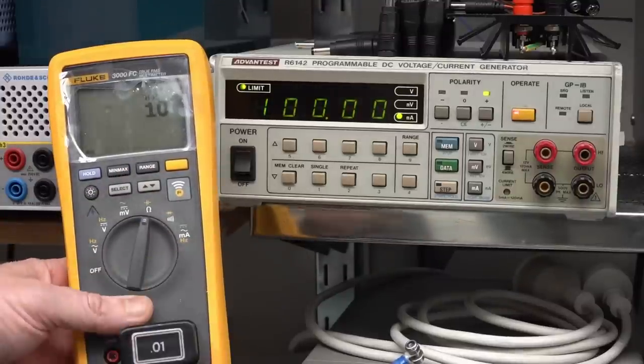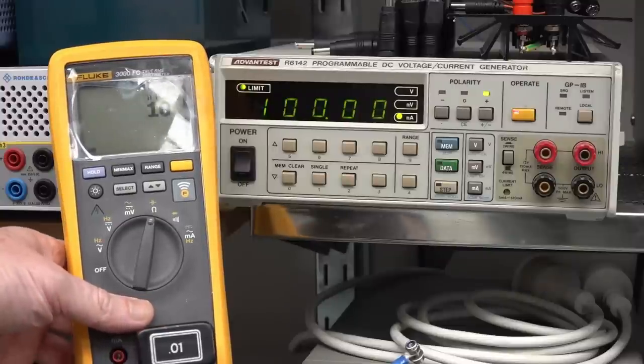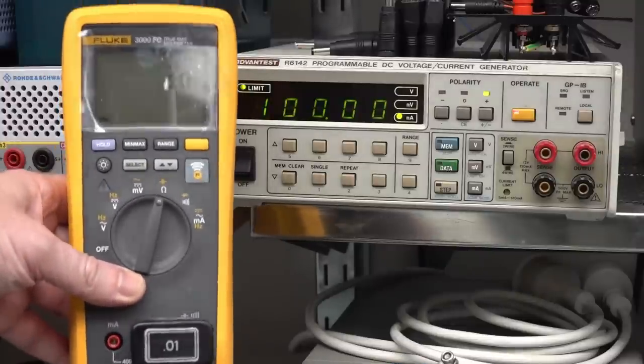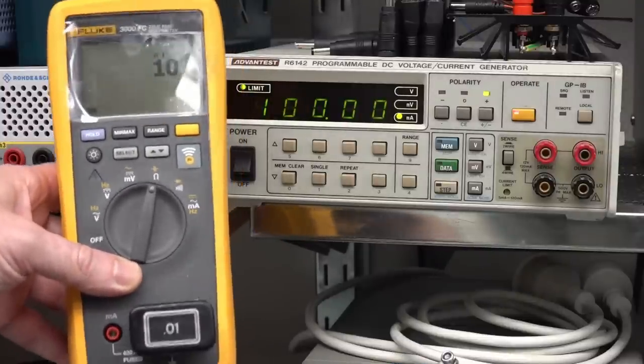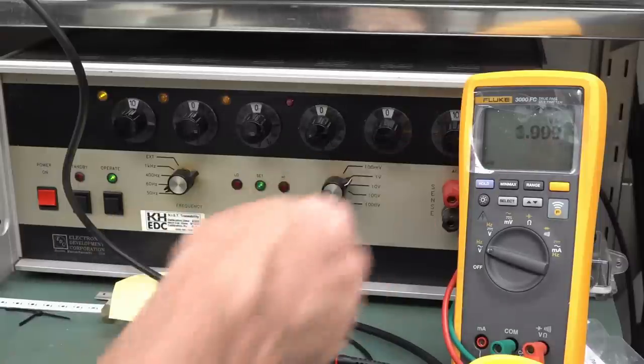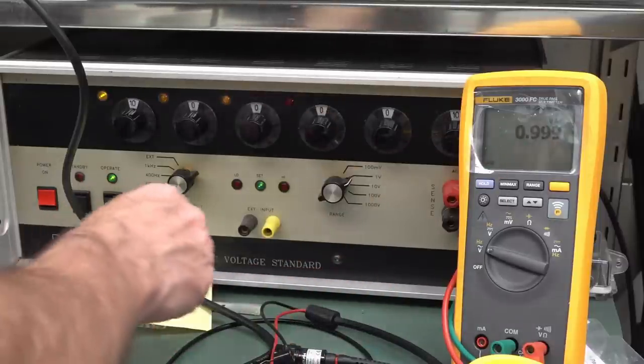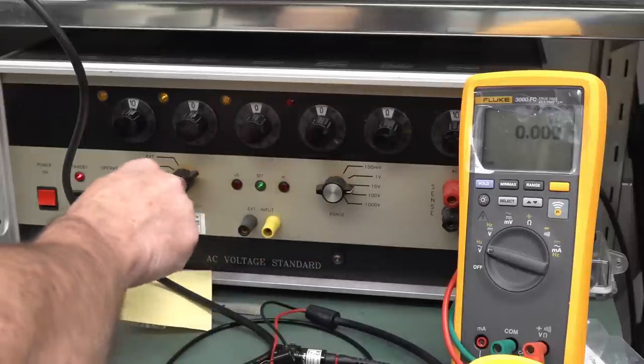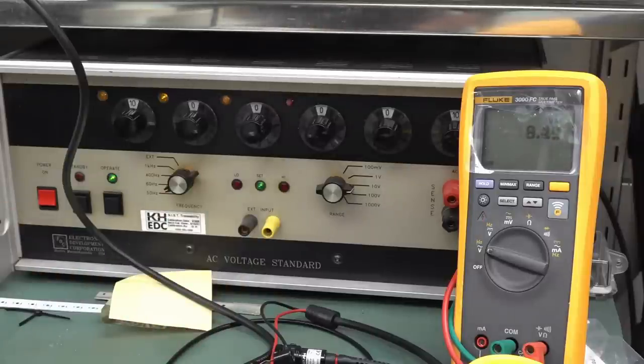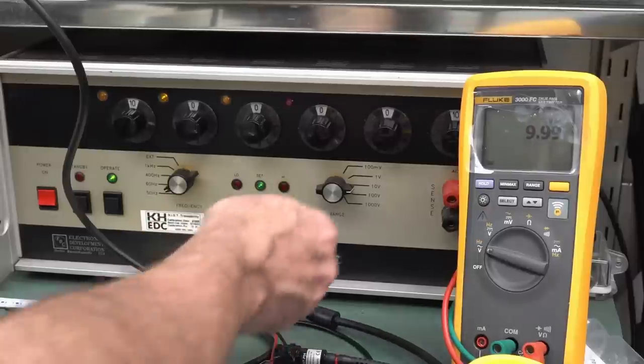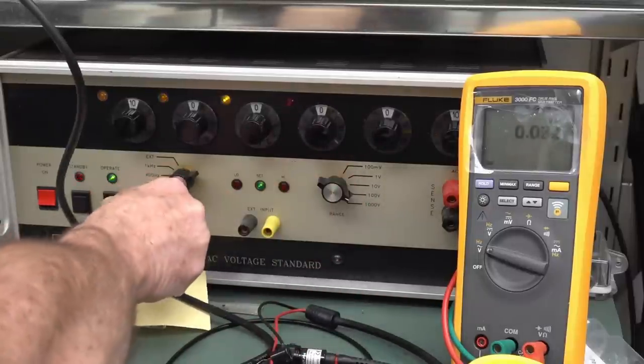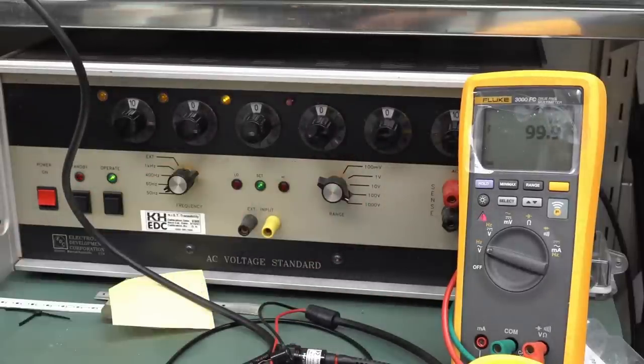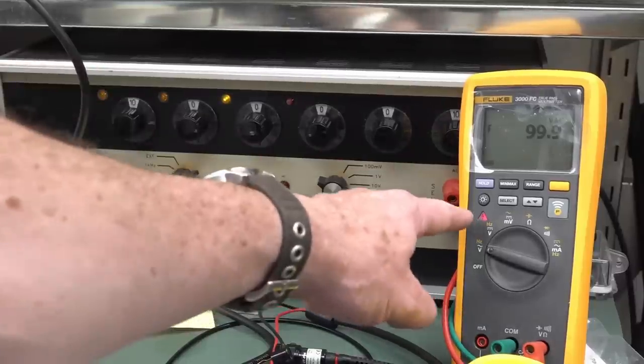And last, but certainly not least, capacitance. There's my capacitance standard, 10 nanofarads. We don't get any more resolution than that, unfortunately. But that works a treat. And my AC reference standard, yep, that's bang on at a volt there. We can go up to the 10 volt range, operate it again, it needs to stabilize. But yeah, there we go. We're getting our 10 volts, no worries. I can even go up to 100 volts if you really want. Everyone's keen. There you go, 99.9. That's almost bang on. And even the high voltage warning LED works.